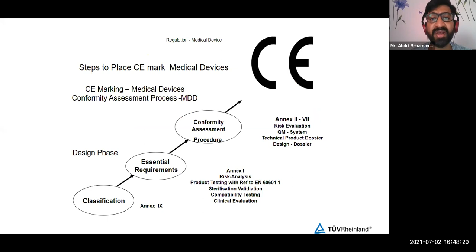We do CE marking, we affix the CE marking. There are different annexures which have to be considered for CE marking. On a high level, like I said, class 1, class 2A, 2B. Class 1 is basically for low risk products, like the pulse oximeters you use nowadays in your homes, or thermometers. Class 2A, 2B are electromedical devices or implants, like your ECG recorders, all this stuff.